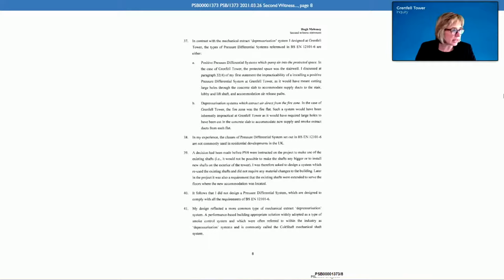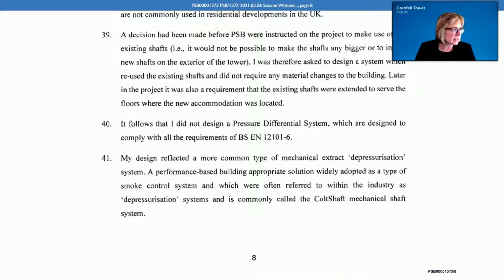I want to look at paragraphs 40 and 41. He's given us some explanation before. He said: it follows, I did not design a pressure differential system which are designed to comply with all the requirements of BS EN 12101 Part 6. And then he says at 41, my design reflected a more common type of mechanical extract depressurization system, a performance-based building appropriate solution widely adopted as a type of smoke control system, often referred to within the industry as depressurization systems, and commonly called the Colt shaft mechanical shaft system.